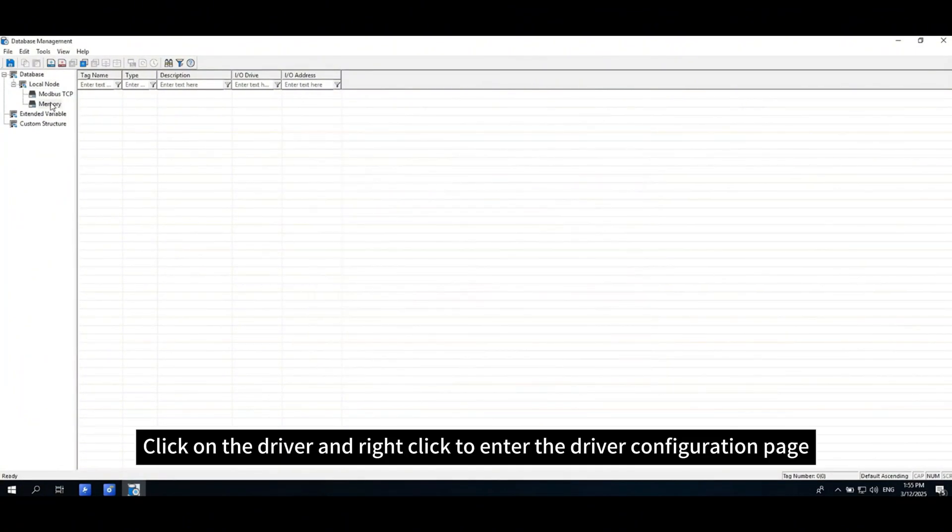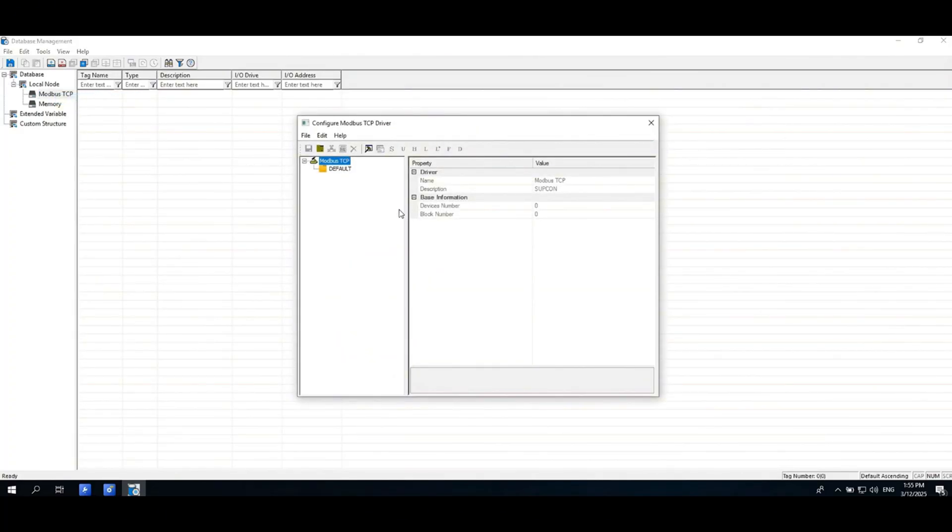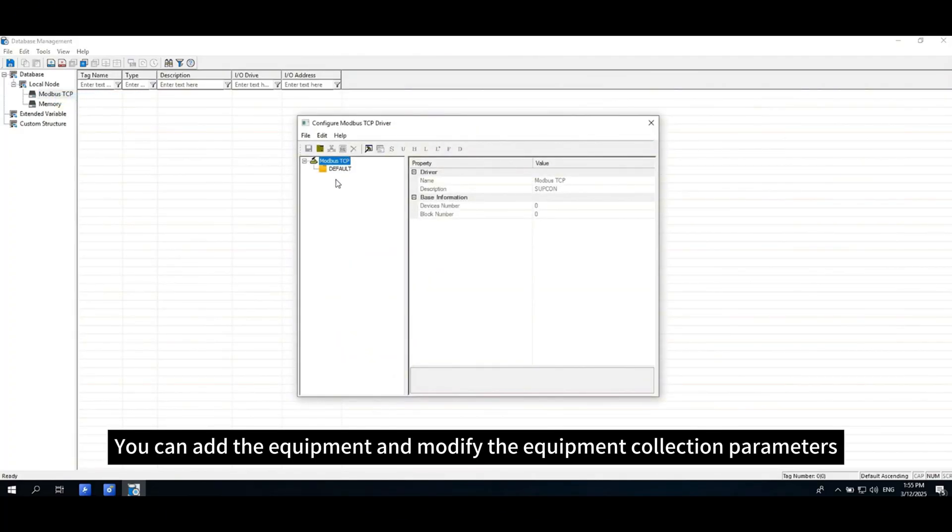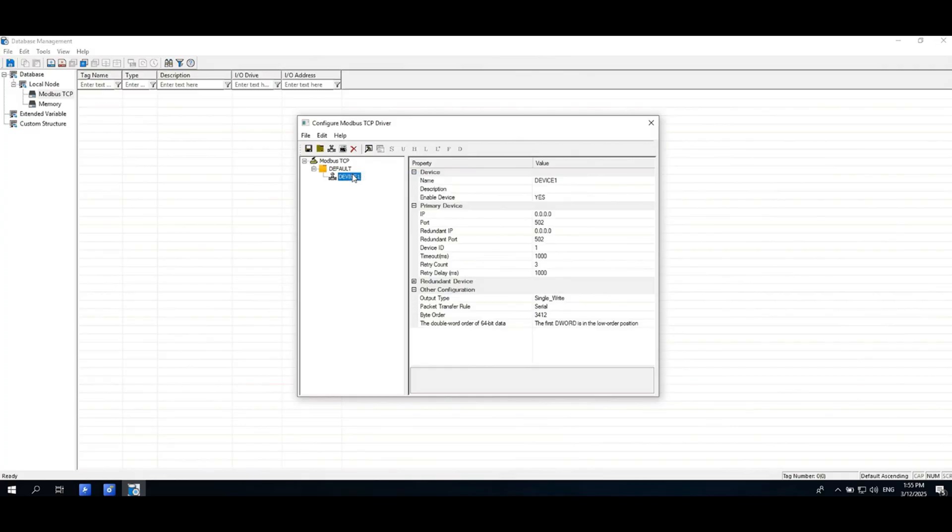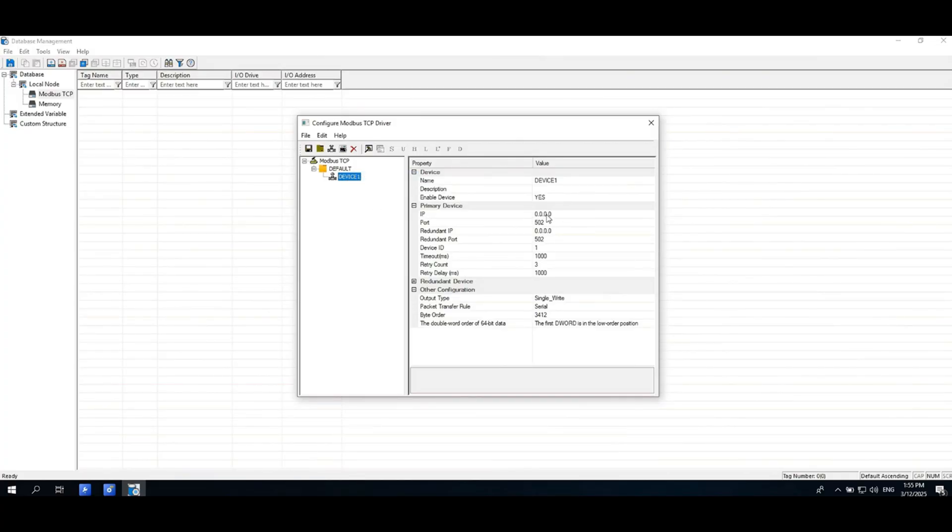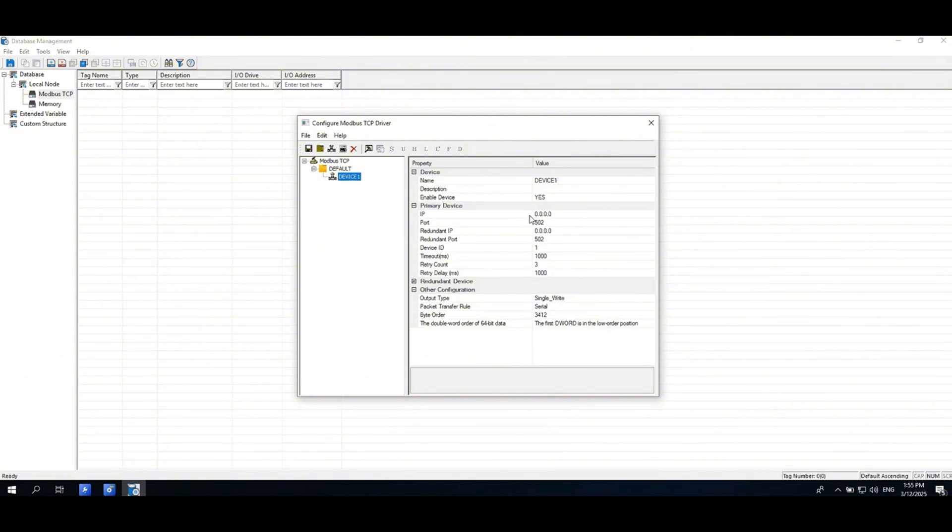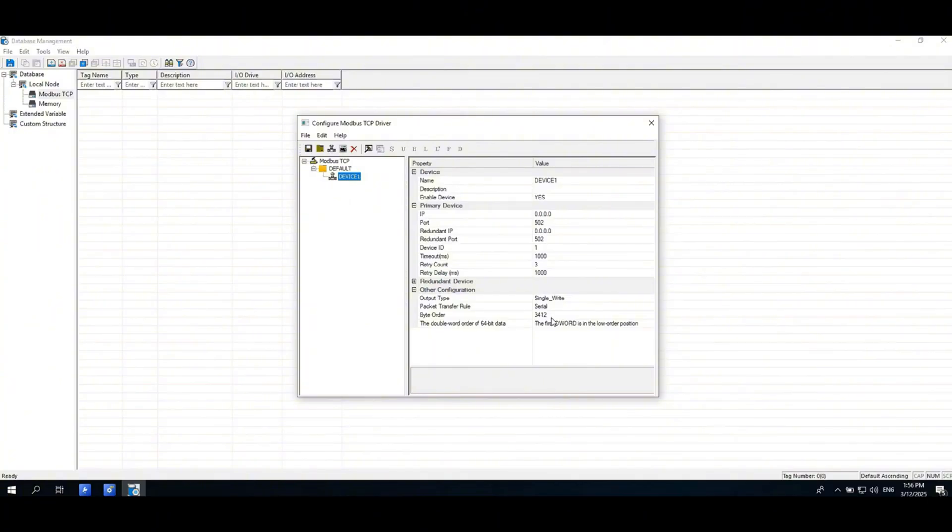Click on the driver and right-click to enter the driver configuration page. You can add the equipment and modify the equipment collection parameters. Click to add device, enter the device's IP address, port number, device ID, and byte order, default 3412.